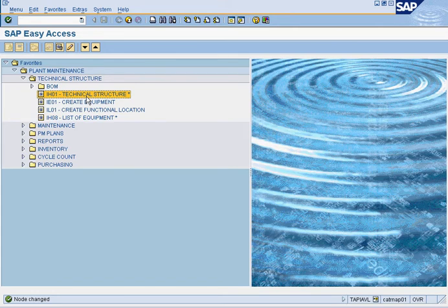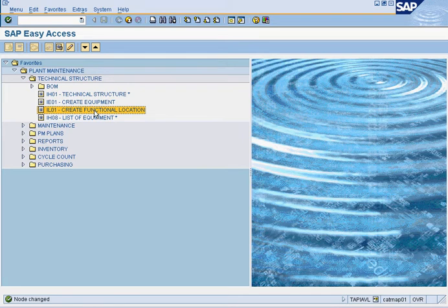The way this is managed is the following: you do the data load and then look at IH01 to view the whole technical structure and see what is there. From there you might make adjustments — either through the technical structure directly, changing equipment or functional locations, or by creating new equipment via IE01 or new functional locations via IL01. You'll also use IH08 to see all the equipment you have: which ones are installed, which ones are not installed, which ones are deleted, and which ones are in storage.